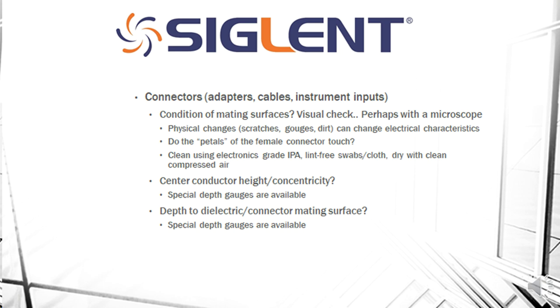First, let's briefly look at some of the major topics here. We want to take a look at the condition of the mating surfaces for all of our adapters and cables as well as our instrument inputs. This is usually a visual check and we're going to possibly use a microscope if we want to take a closer look at those surfaces.